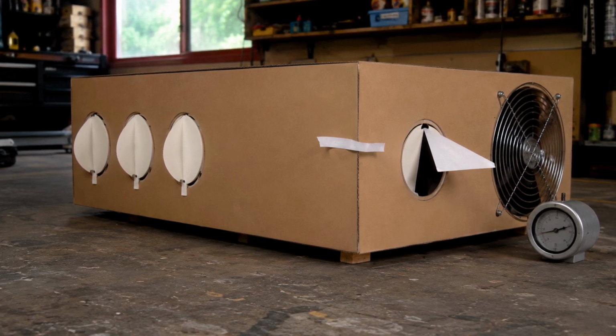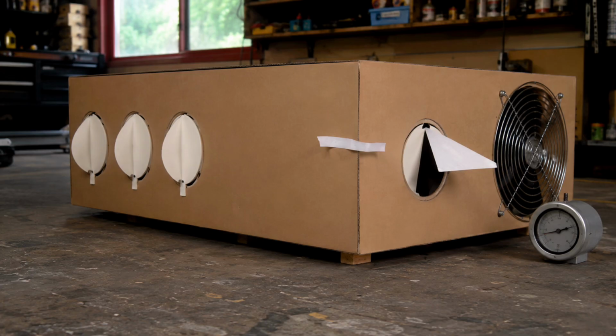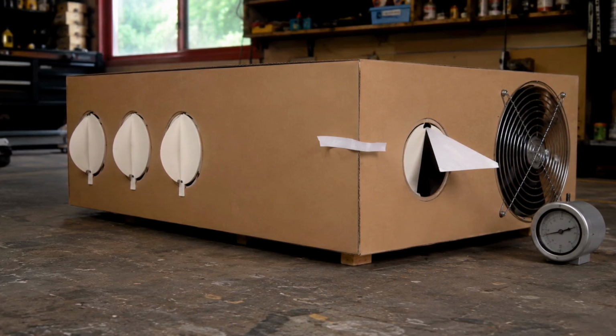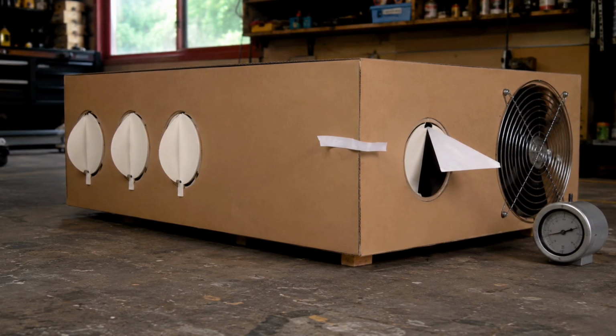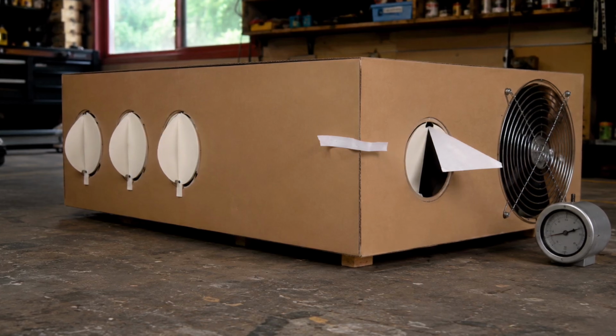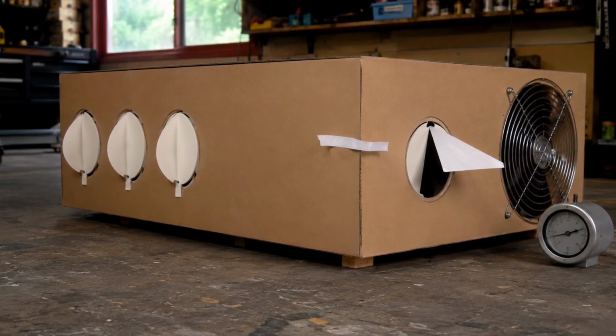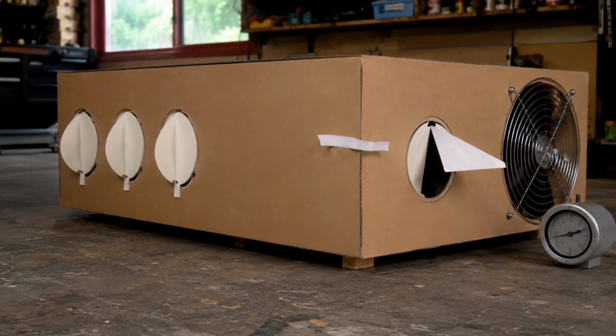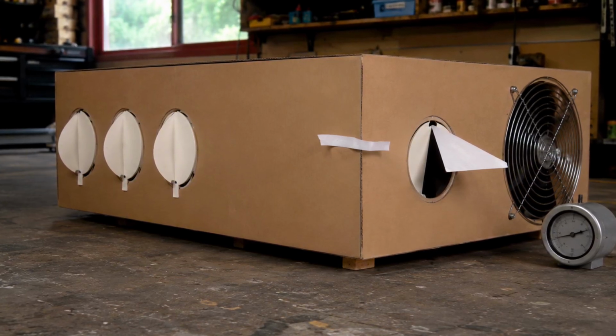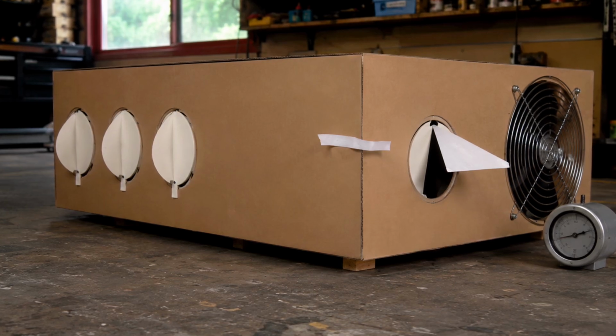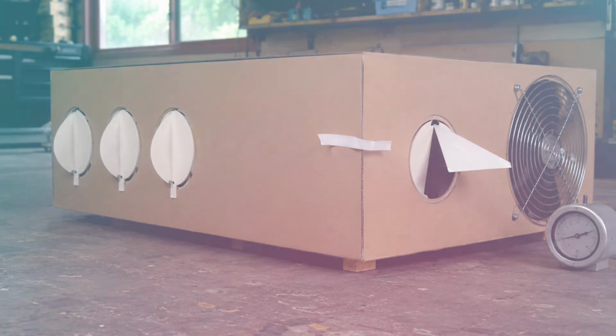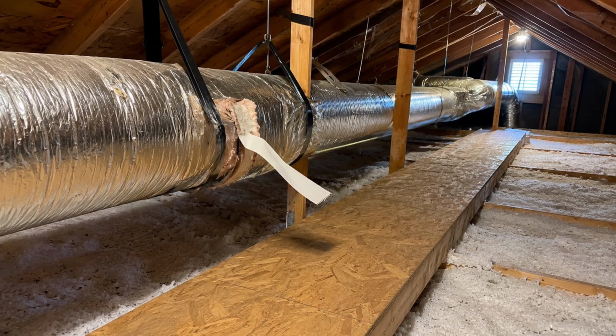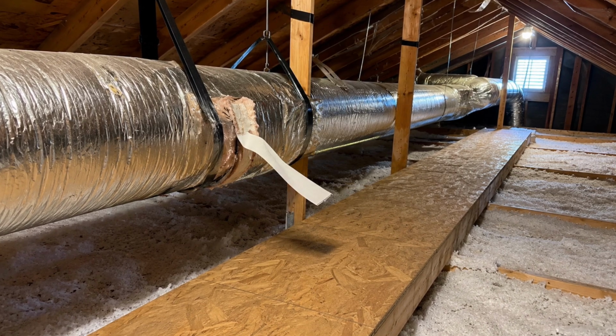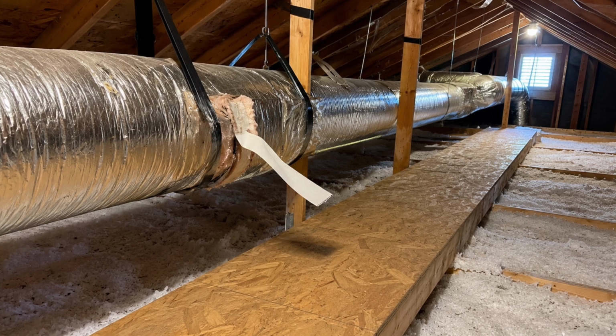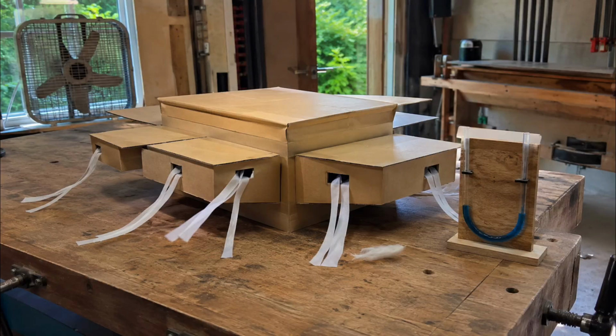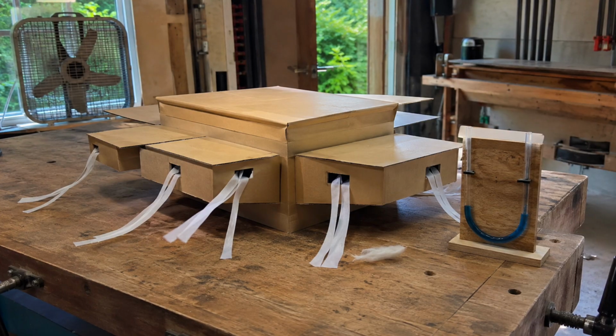And now the part of the demonstration that can cost money in a real house. Feel along this taped seam. With all 4 holes open, there is barely a flutter. Cover 3 holes, raise the pressure inside the box, and more air pushes through the weak joint. Your real ducts have joints and seams too, sometimes running through an attic, crawl space, garage, or other place you never meant to cool. The amount of leakage depends on how well those ducts are sealed. But if a gap already exists, more pressure across that gap can drive more air through it. That is, conditioned air you paid for that never reaches any room.